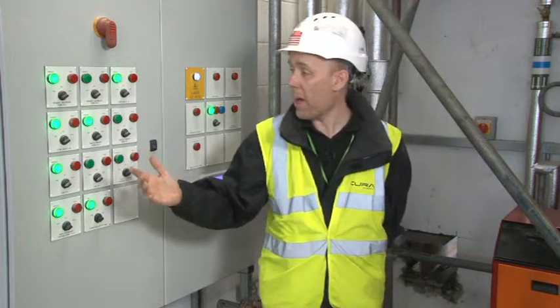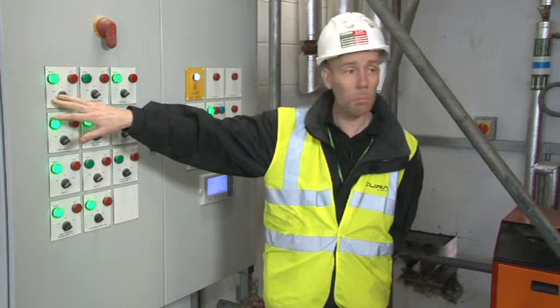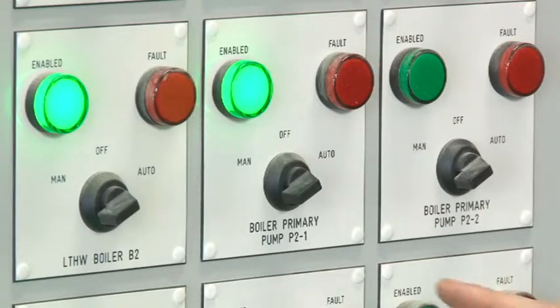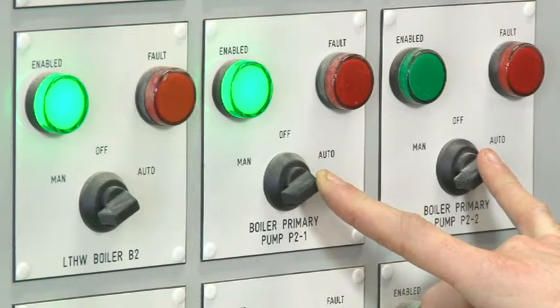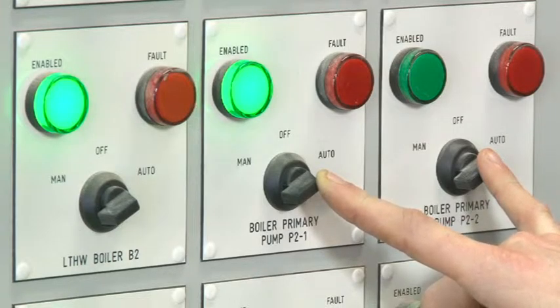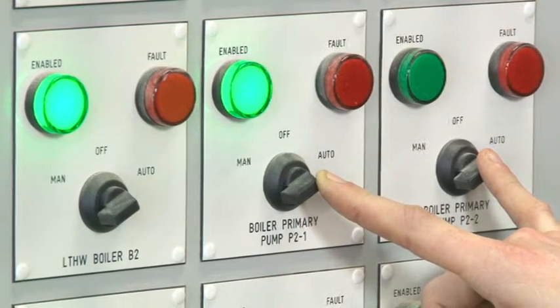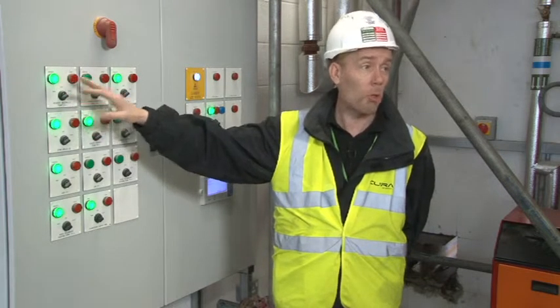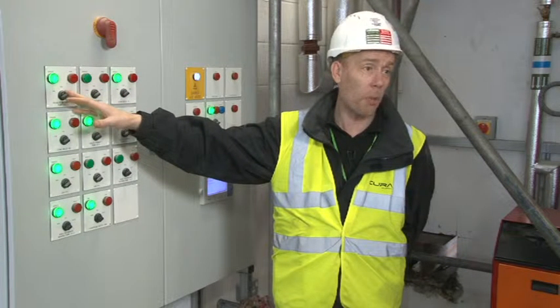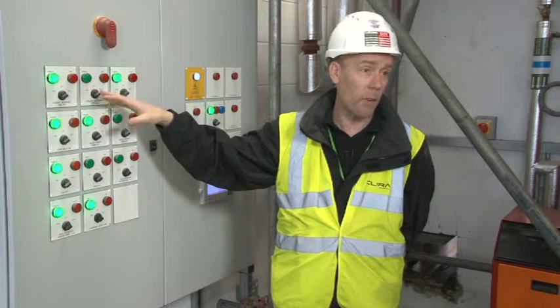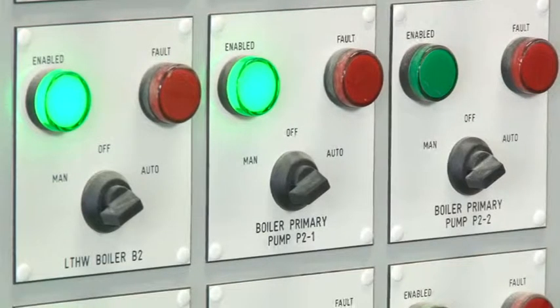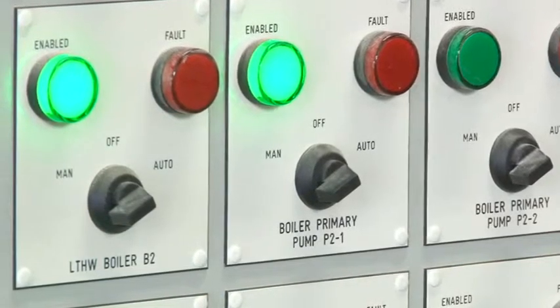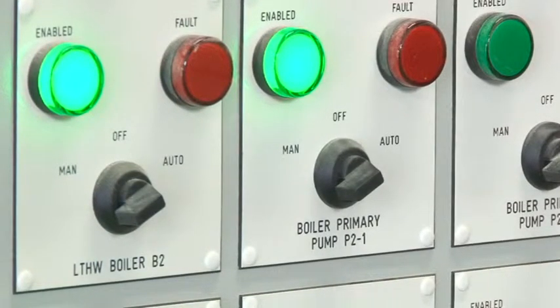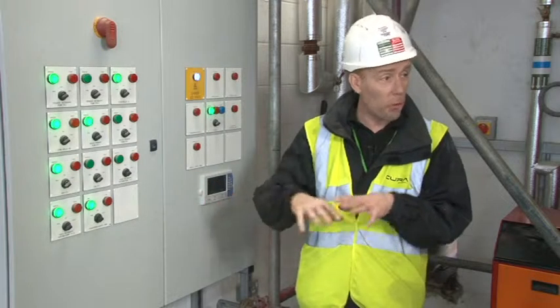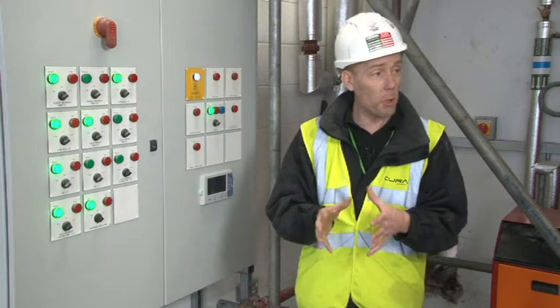All of the switches on the panel have a manual, off and auto status. If for any reason the computerized section of this fails, you would still be able to operate the site and building under manual, so you could still maintain heating to all of the apartments and extract ventilation, etc. for the building. Normally when you come in here, all of the switches will be in auto. Some of the switches you'll notice are in auto and the green lights aren't on. These are units that are in standby should the main unit not be operating.